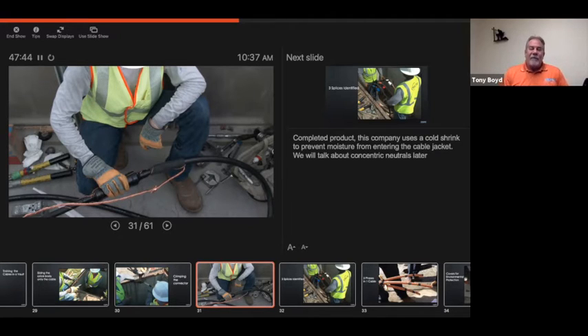Why is it a bleed wire? Well, I mentioned the cable and the stresses and creepage distances. So first off, our splice body is keeping all of the stress that's coming through that insulation outwardly and evenly. But like I mentioned earlier, you also have that little bit of amperage loss, that creepage distance that's going through the insulation, and it needs to have that semiconductor shield on top. Now, that splice body could actually carry some amperage. And carrying a little bit of amperage is no big deal unless we get some voltage. So what I'm going to talk about at the end here is those concentric wires. And they're connected. So until they're bonded together here in the middle, they create a different hazard that I'll cover in about 10 minutes.